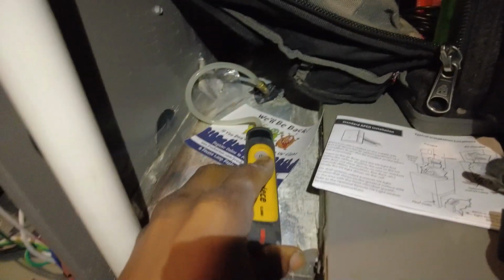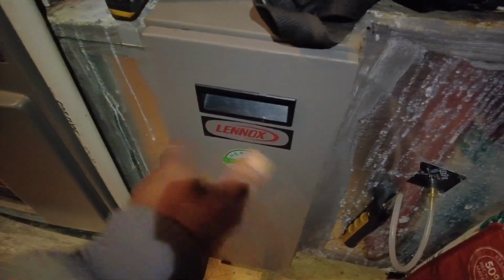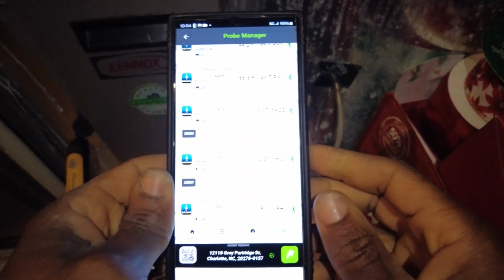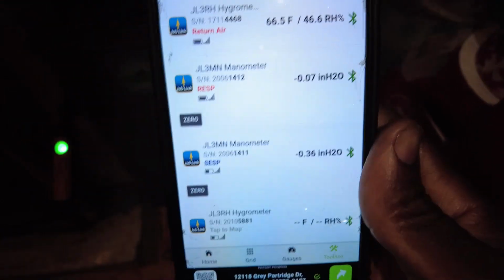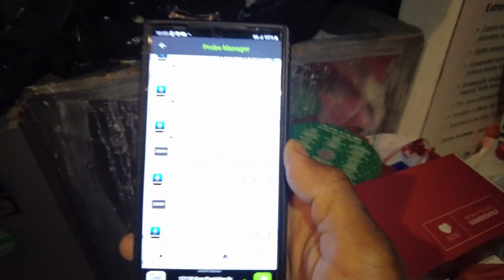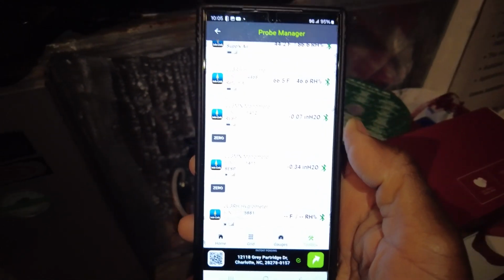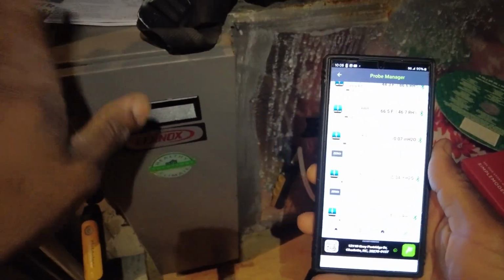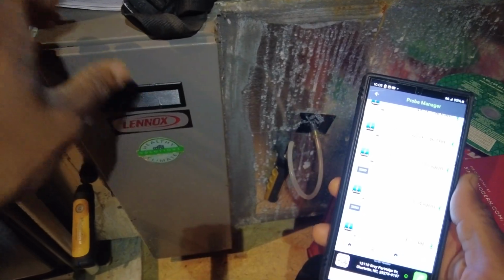So I'm adding one on this side of the filter, as you see. What we're doing is measuring our pressure drop across this filter media. As you can see, it's not bad at all. We've got a 0.07 on this side of the filter, meaning the only pressure drop the ductwork is causing in this plenum box is less than 1/10 of an inch of water column, which gives us so much headroom to work with. So we can literally add another 20 by 25 by 5.